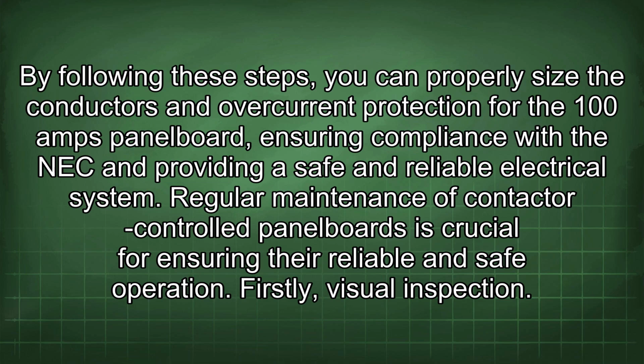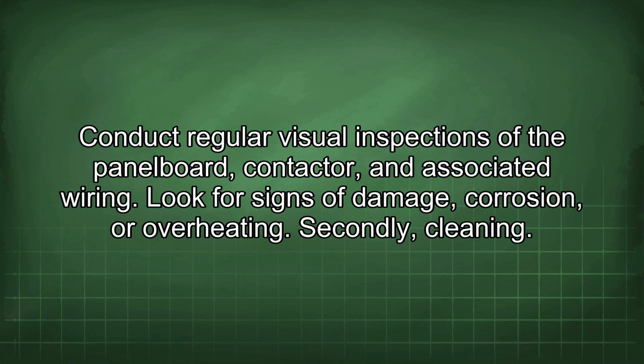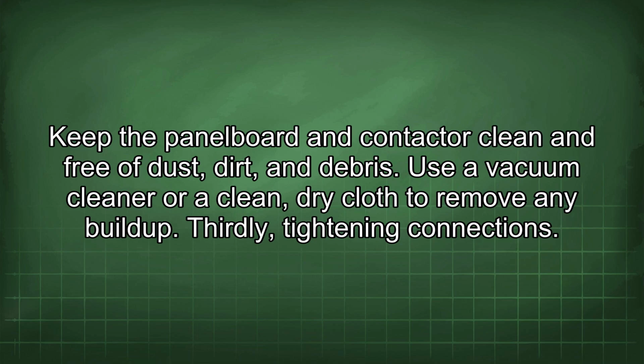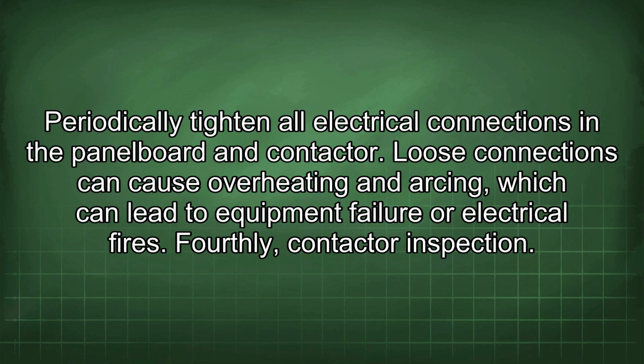Regular maintenance of contactor-controlled panel boards is crucial for ensuring their reliable and safe operation. Firstly, visual inspection. Conduct regular visual inspections of the panel board, contactor, and associated wiring. Look for signs of damage, corrosion, or overheating. Secondly, cleaning. Keep the panel board and contactor clean and free of dust, dirt, and debris. Use a vacuum cleaner or a clean, dry cloth to remove any buildup. Thirdly, tightening connections. Periodically tighten all electrical connections in the panel board and contactor. Loose connections can cause overheating and arcing, which can lead to equipment failure or electrical fires.